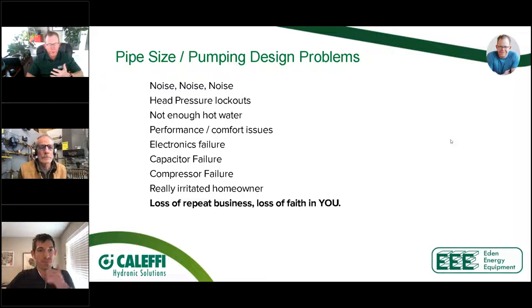And again, speaking from two decades of experience, the next thing you're going to tell me is, I don't know what's wrong with this heat pump, but I put 10 capacitors in it. It's like, okay, there's nothing wrong with the heat pump. That compressor is just getting pushed outside of its envelope and the start components are failing because they're not designed to start-stop 6,000 times a day. They're supposed to start-stop 20 times a day. And then of course the real doozy is you end up with a really expensive failure.